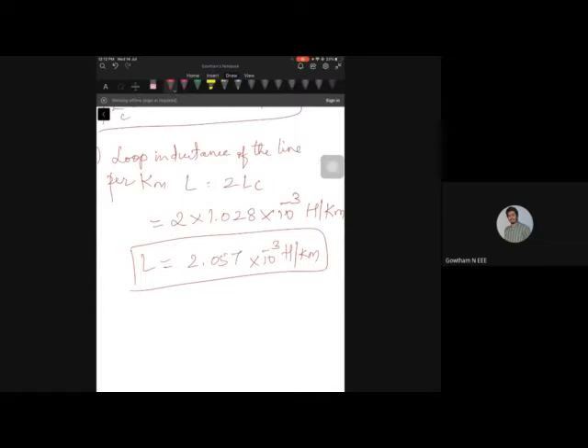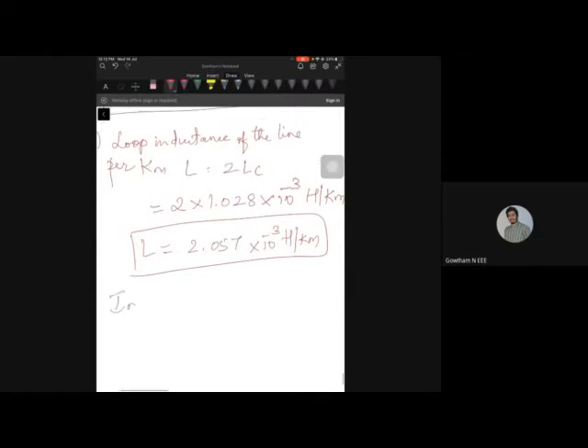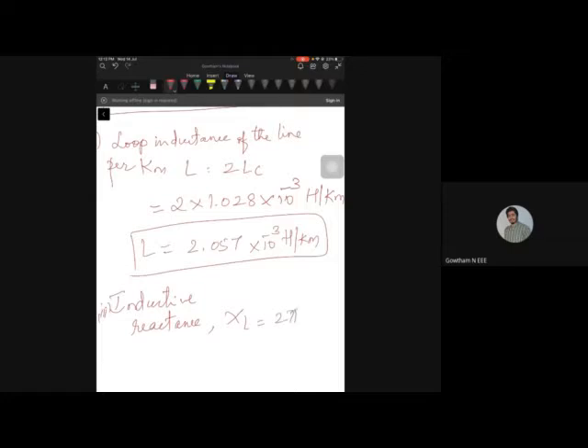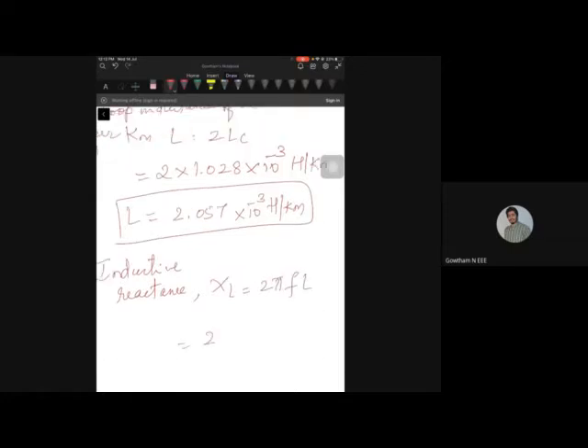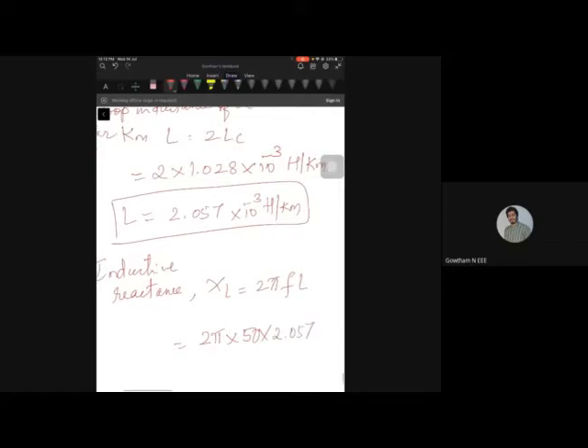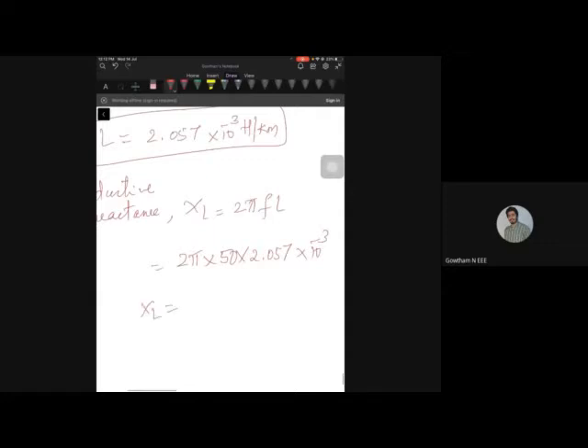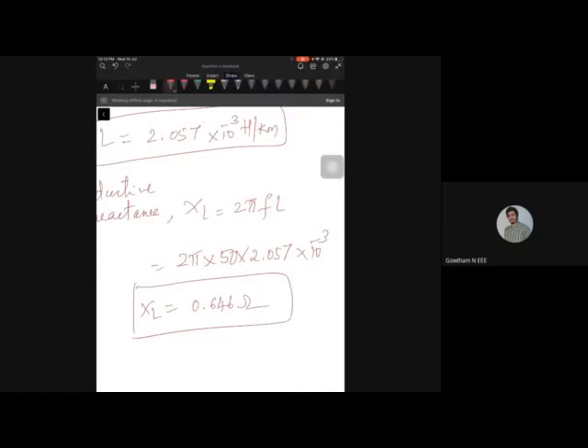The third quantity is inductive reactance. XL = 2πfL = 2π × 50 × 2.057 × 10⁻³ = 0.646 ohms per kilometer. So all three values are found: inductance of each conductor, loop inductance (twice the individual), and inductive reactance.